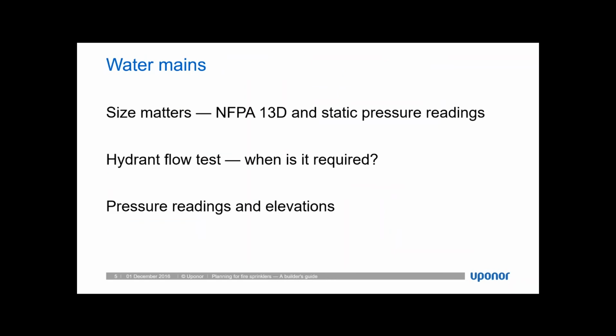Speaking of the water main, since that's where we get started for any sprinkler system, the size of the water main does have an impact on how we go about designing the sprinkler system. NFPA 13D allows for any water main 4 inches or larger. You can use the static pressure alone to compare the hydraulic demand of the sprinkler system to the available water pressure. For 13R or 13 systems, it is often required that a full hydrant flow test be conducted, where you measure both the static pressure and the residual pressure when flowing a large amount of water, usually out of a nearby fire hydrant. This is used to establish a curve that will tell you how much water pressure you have available at various flows.